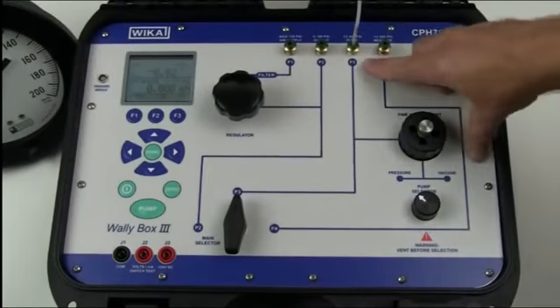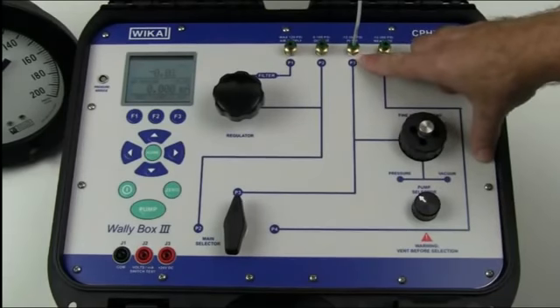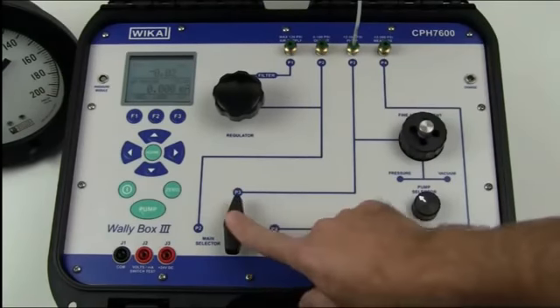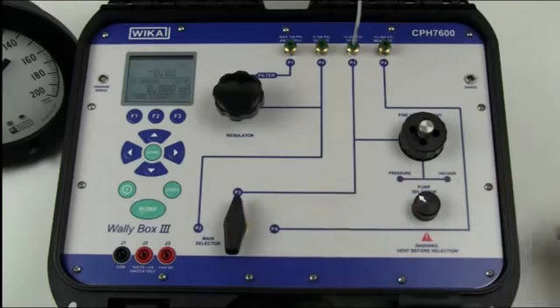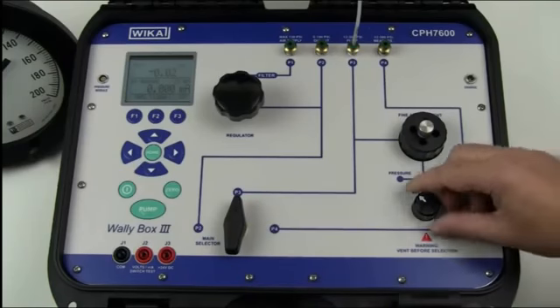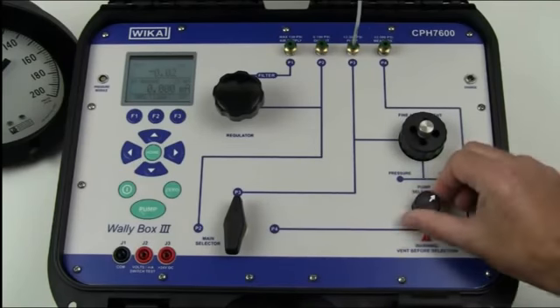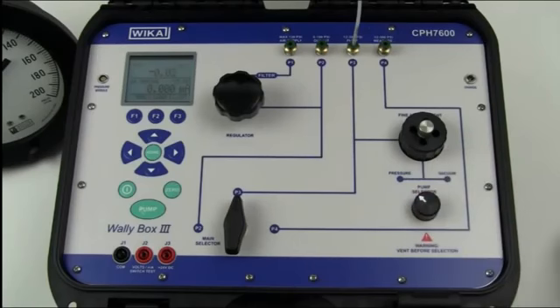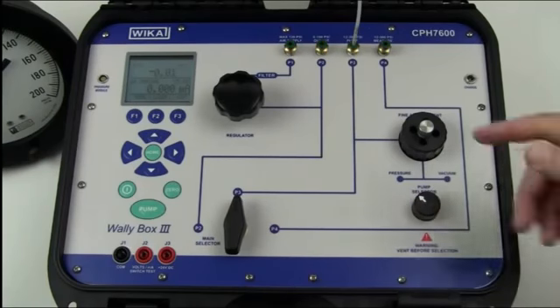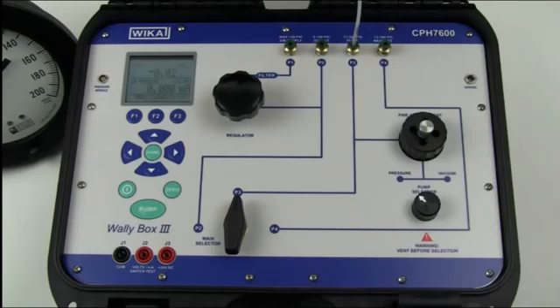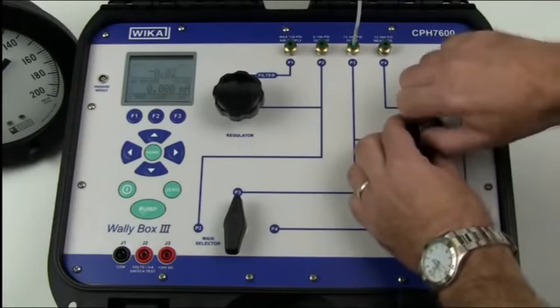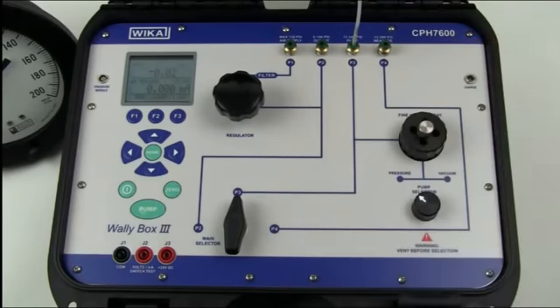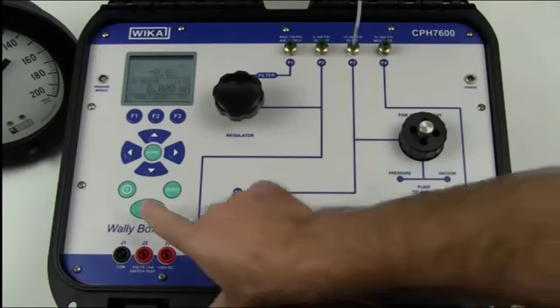We have already connected our gauge on position P3. The main selector switch must be in position P3, and then because we're going to a positive pressure, you must make sure that the pump selector switch is on pressure and not vacuum. We have already zeroed the display, we need to make sure that the vent is closed. We are then able to go over and start pumping it up.